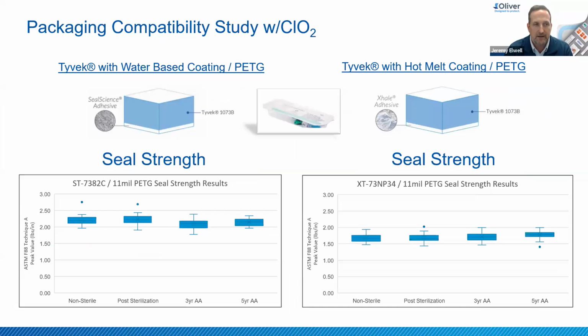And then we look at coated Tyvek with tray material, in this case, 11 mil PETG. So we're doing seal coupons. We're not taking fully formed trays in this study, but small seal coupons just to show seal strength over time and any kind of visual anomalies that we may see. But in this case, both a seal science or water-based type coating and a hot melt type coating, they both showed compatibility and no adverse effects over time.